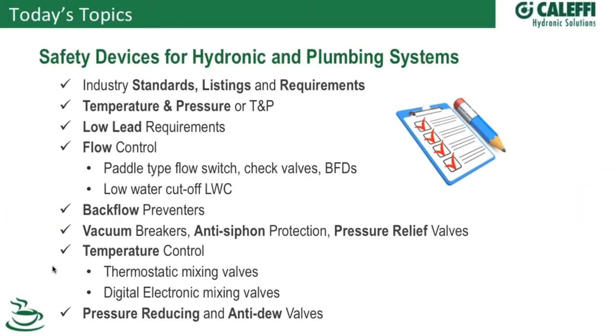Today's topic: I wanted to take a look at all the different safety devices that you see in the plumbing and hydronic field. As I started getting into this, I realized that some of these devices are going to be required by a manufacturer when they sell you a product, like a boiler, that will come with a valve on it. A water heater typically comes with a valve that was sized and specified for the product. Some of the valves we'll talk about today have to do with temperature and pressure, like a T&P type of valve on a water heater. Some will be pressure only. We're going to talk about valves that would require low lead certification if they're used on domestic water.